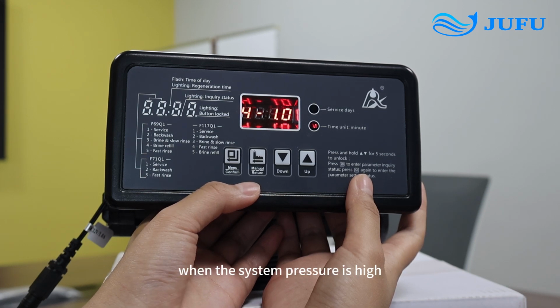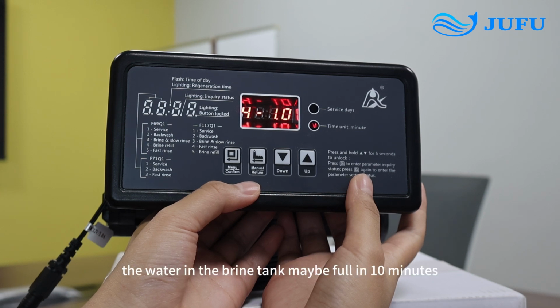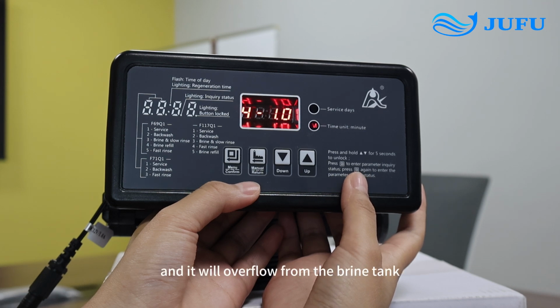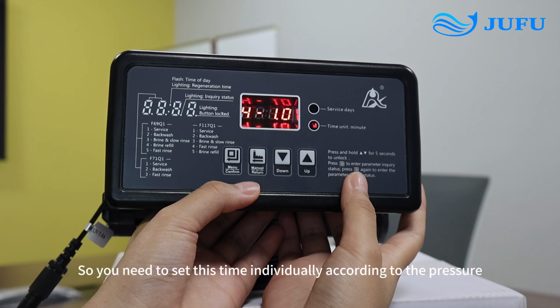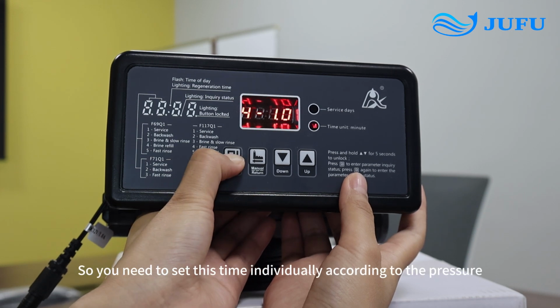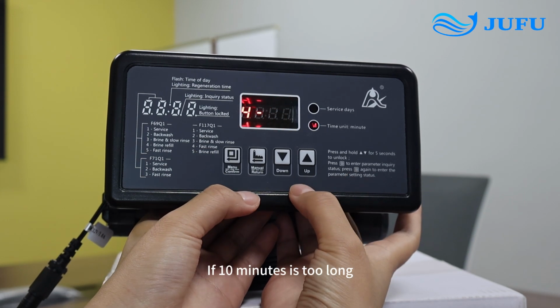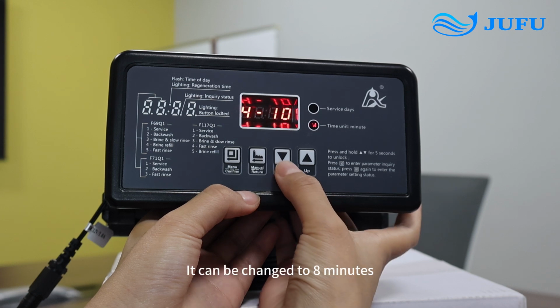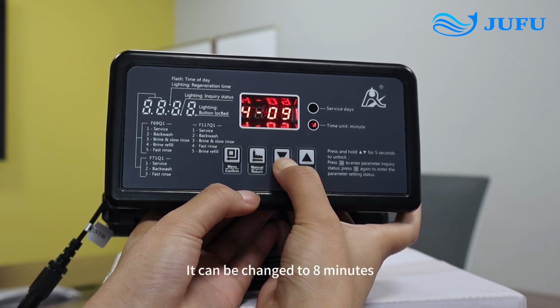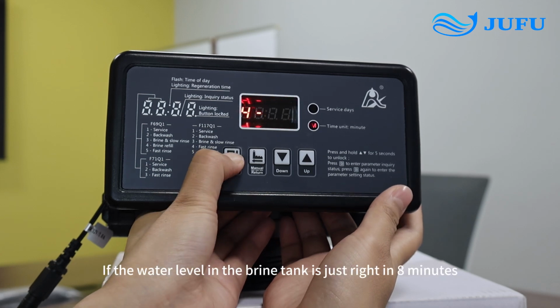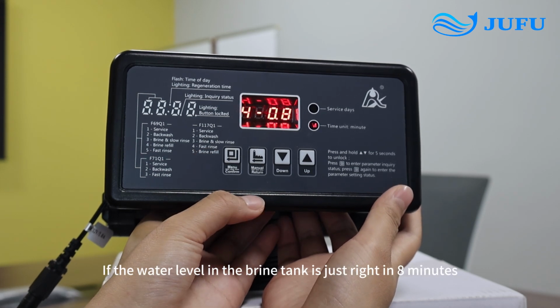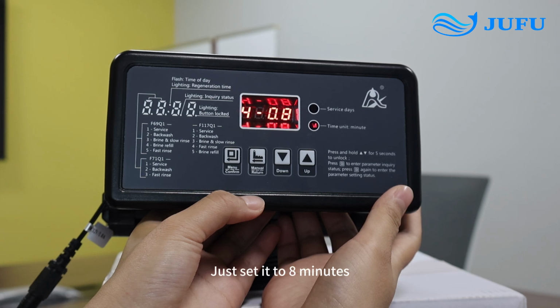In the same principle, when the system pressure is high, such as 3 kg, the water in the brine tank may be full in 10 minutes, and it will overflow from the brine tank. So you need to set this individually according to the pressure. If 10 minutes is too long, it can change to 8 minutes. Then observe if the water level in the brine tank is just right in 10 minutes. Just set it to 8 minutes.